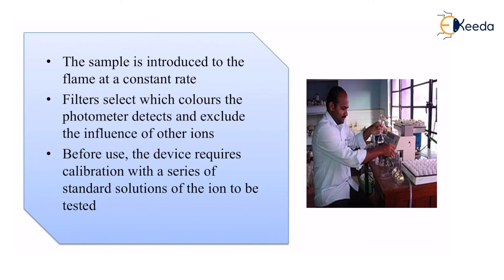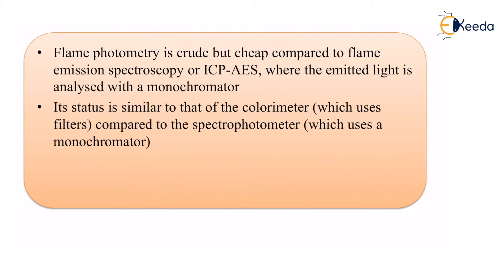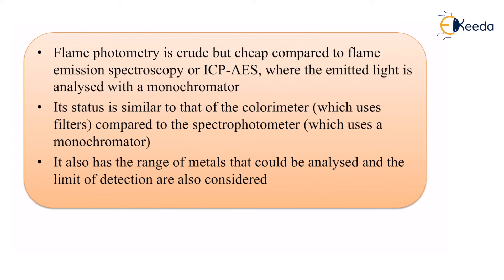Before use, the device requires calibration with a series of standard solutions of the ions to be tested. Flame photometry is crude but cheap compared to flame emission spectroscopy or ICP-AES, where the emitted light is analyzed with a monochromator. Its status is similar to that of a colorimeter, which uses filters, compared to a spectrophotometer, which uses a monochromator. It also has a range of metals that could be analyzed, and the limits of detection are also considered.